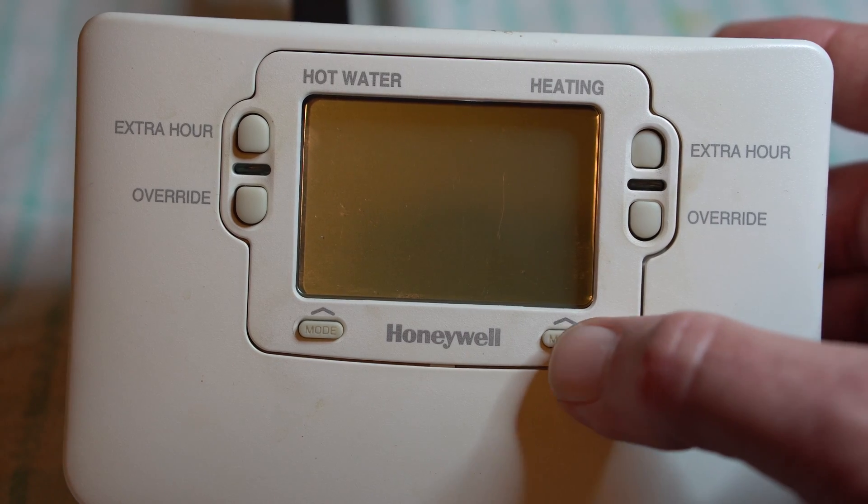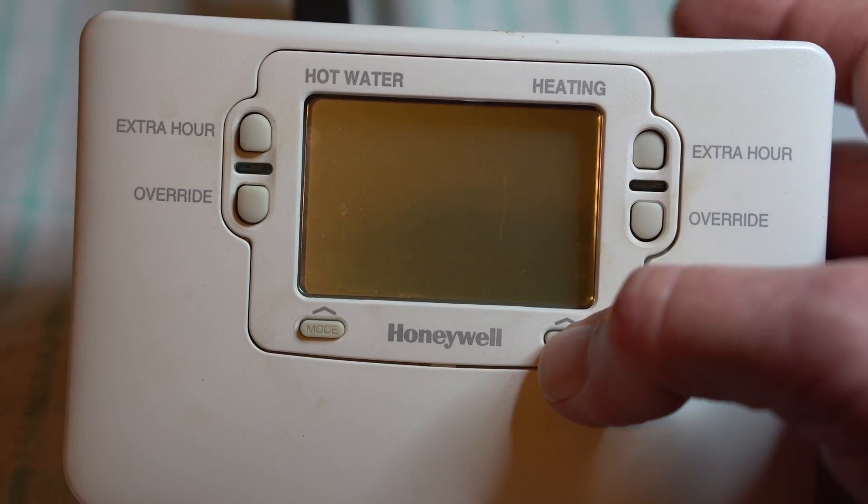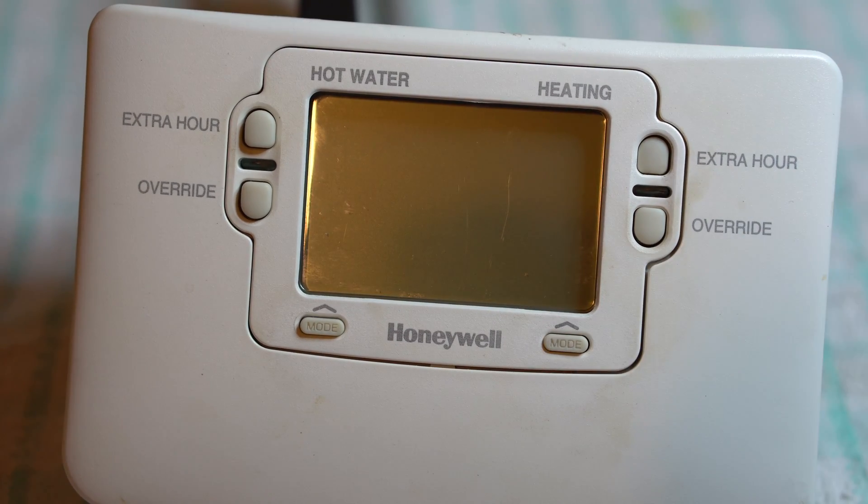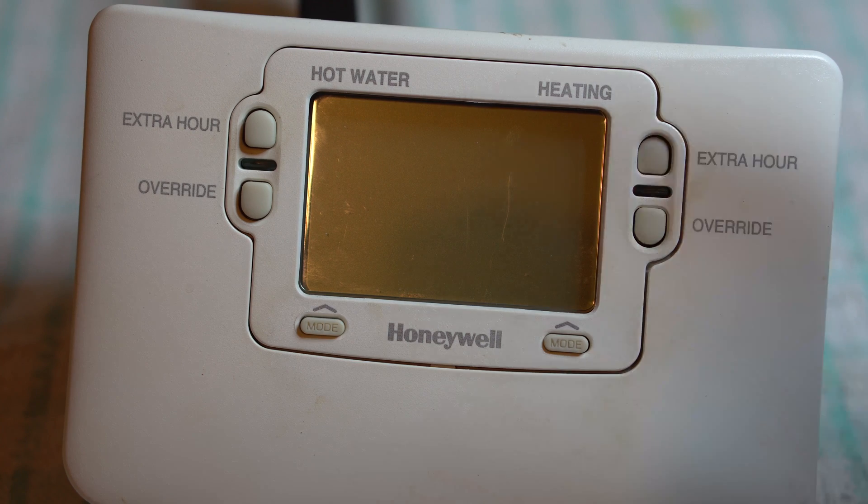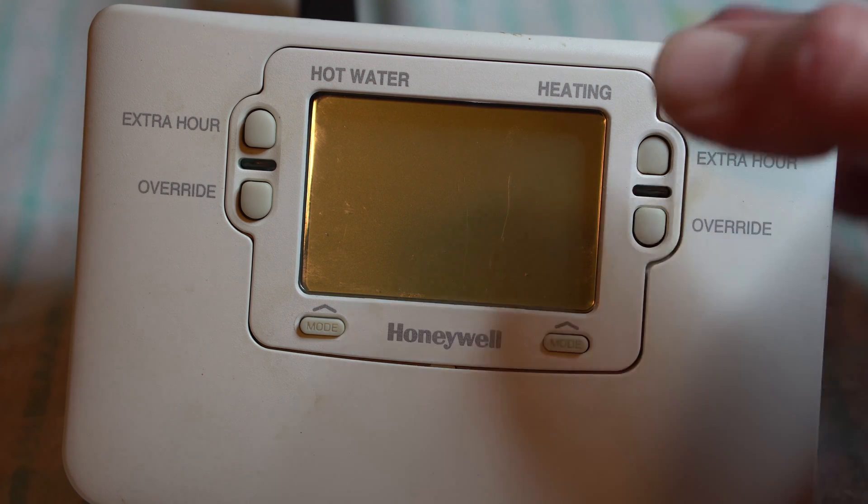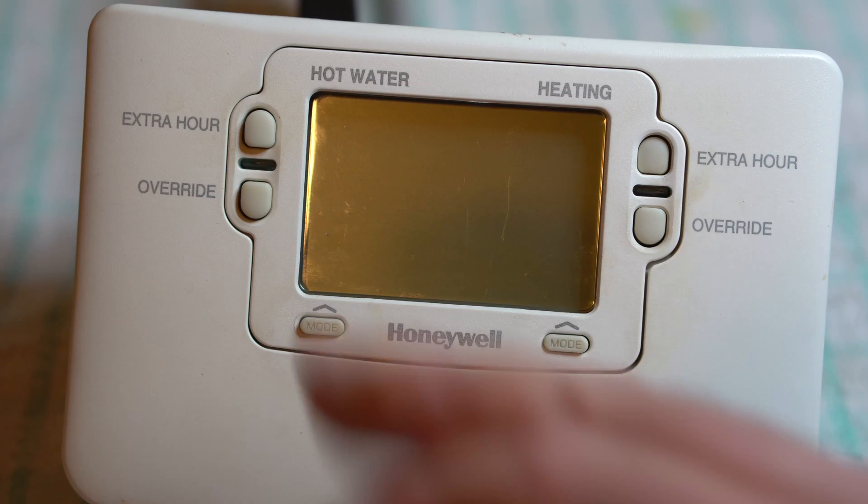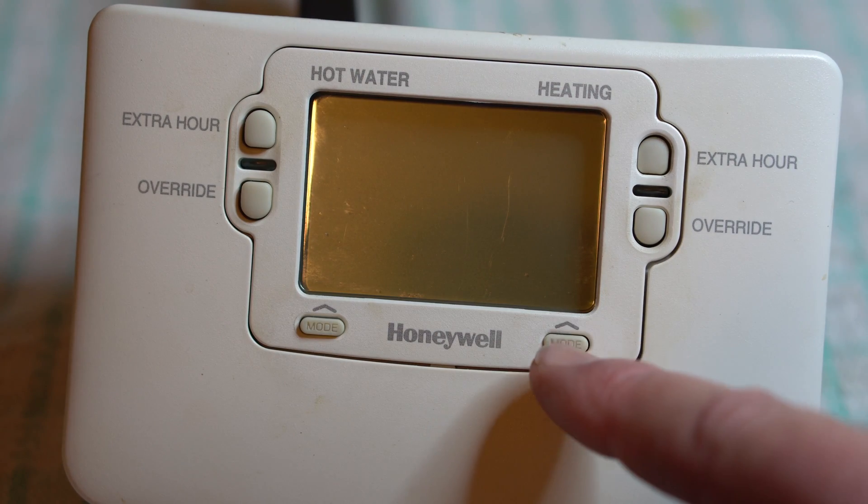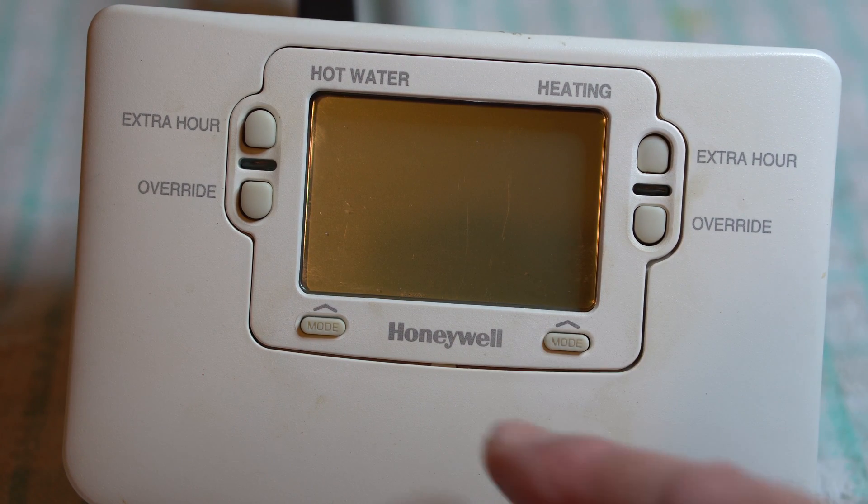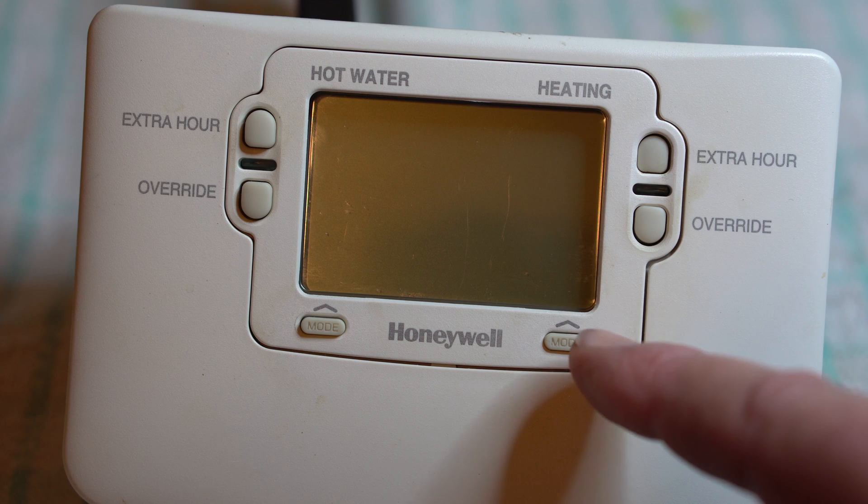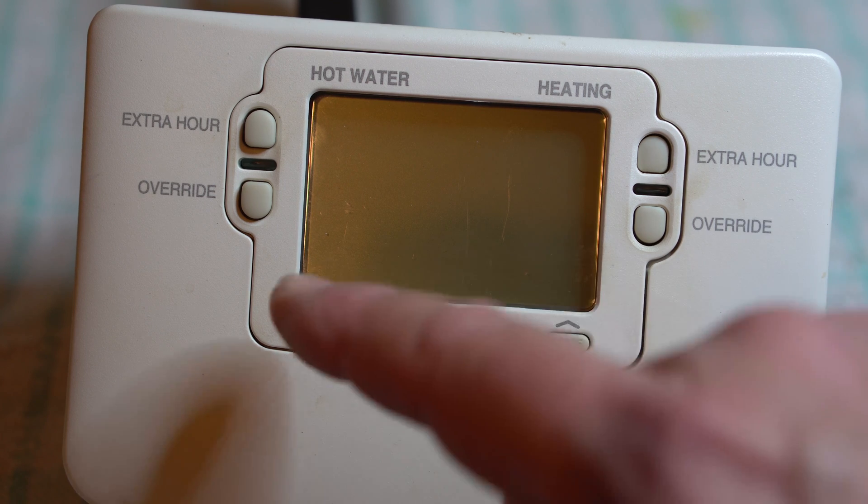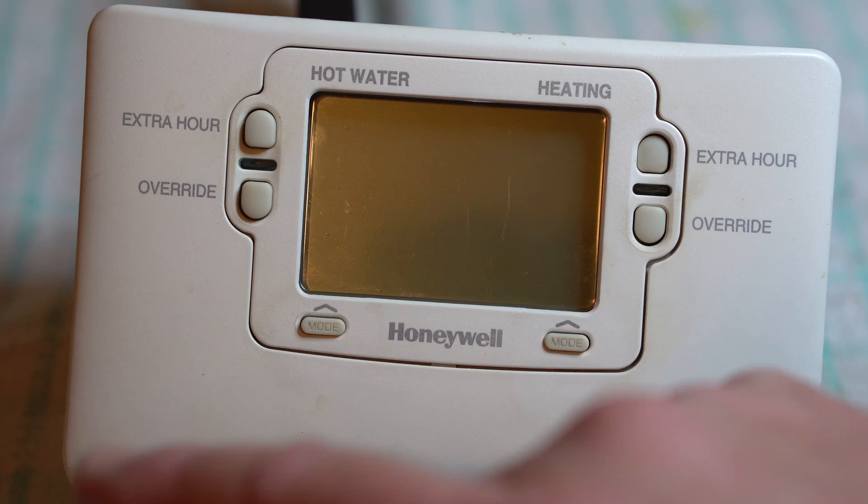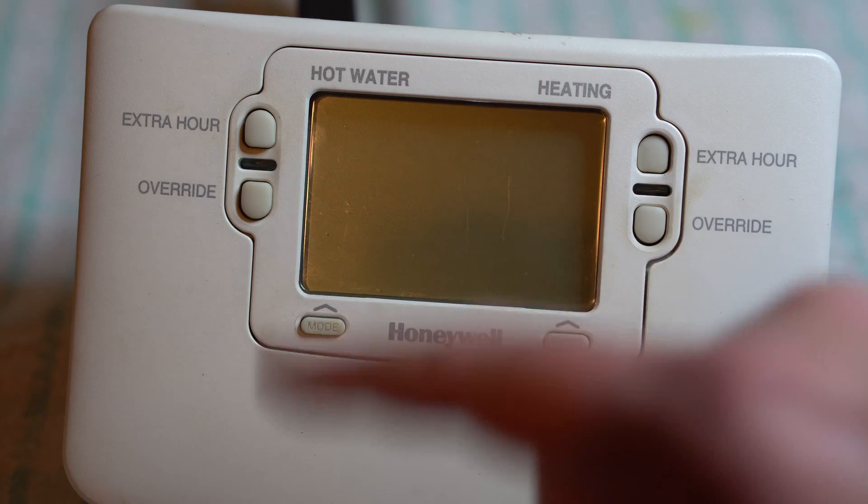If she tried to just have the central heating, over the last few months, sometimes the heating would come on, other times it wouldn't. If you don't turn the hot water on, turn the central heating on first. The central heating should bring on a water pump, and then fire up the boiler, and it wouldn't.